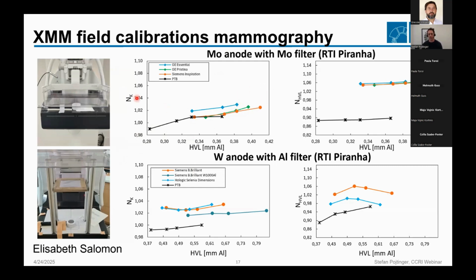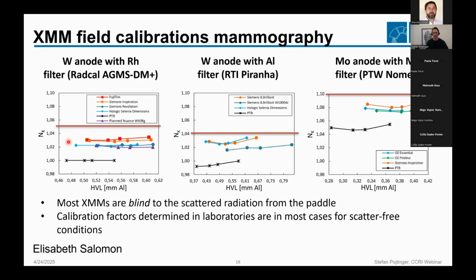And as you can see here for air kerma, for some devices, for example, for the Siemens Inspiration and also for one of the GE devices, we have a very good alignment of the calibration factors between clinic and laboratory. But that's not always the case. We also found some differences here, for example, for the tungsten aluminum combination with the Piranha. And that's only for air kerma. If you're going to look at other quantities that can be measured with XMMs like HVL, deviations can be larger, as you can see here on the right. So there are many different devices, and we tested a lot of them. And I think right now we are confident to say, because we tested so many devices and XMMs, that the differences between the clinical beams and the laboratory beams, when it comes to deviations of calibration factors determined in a laboratory condition compared to a clinical condition, are somehow within 5%.